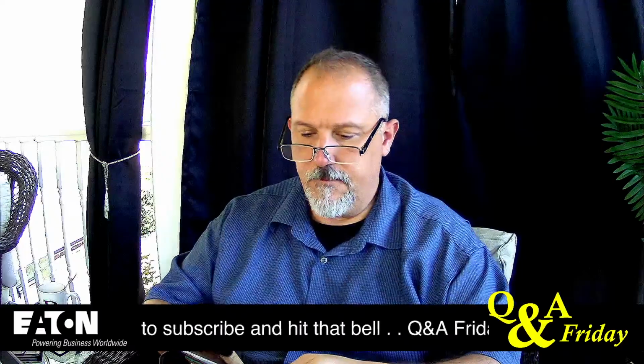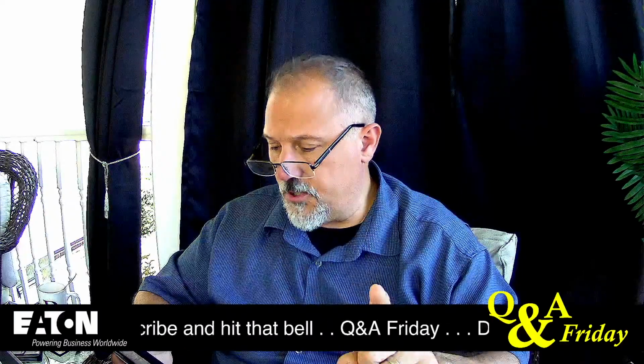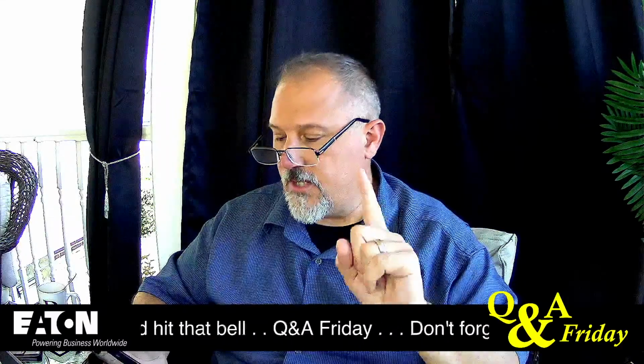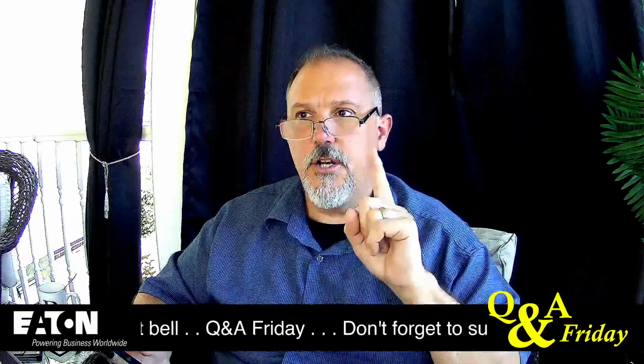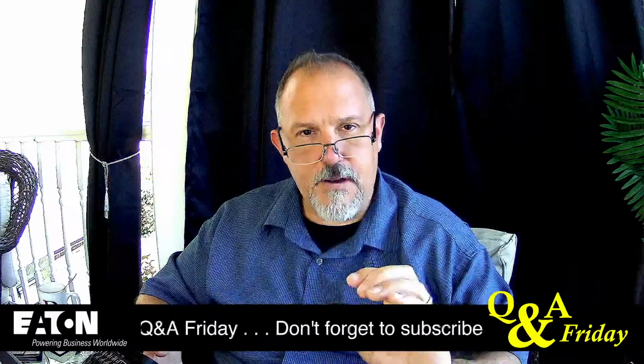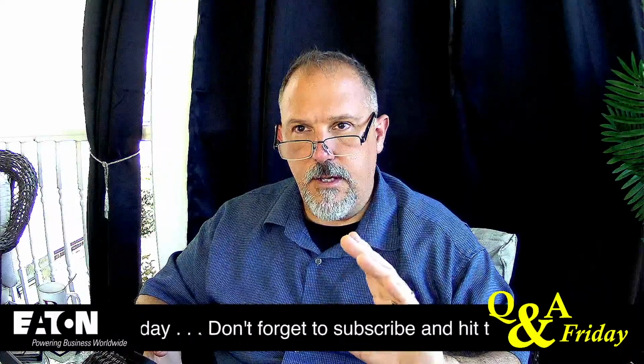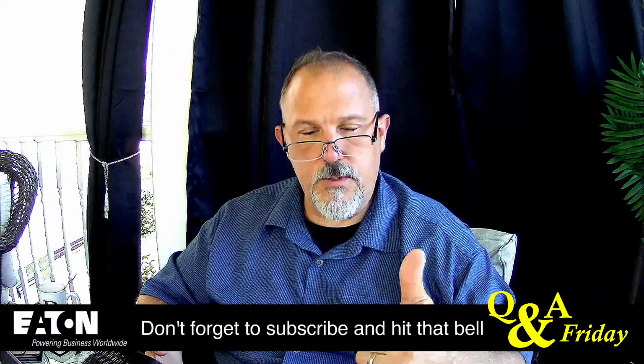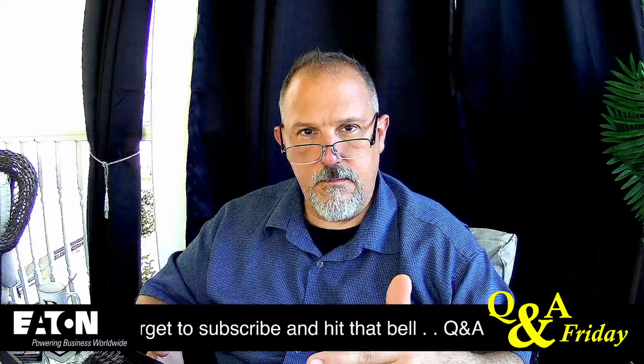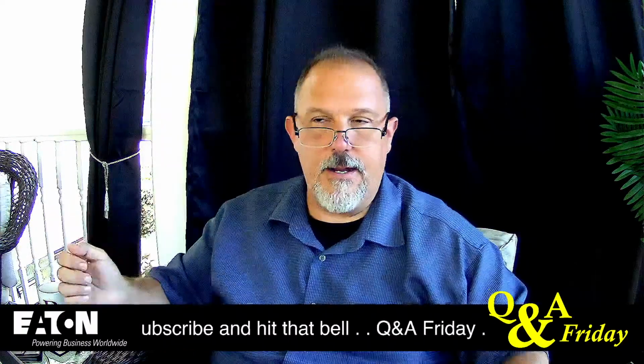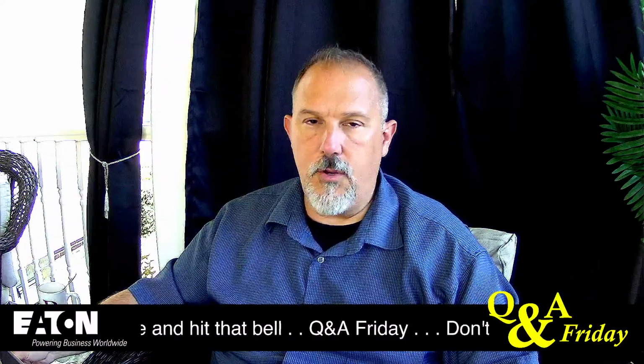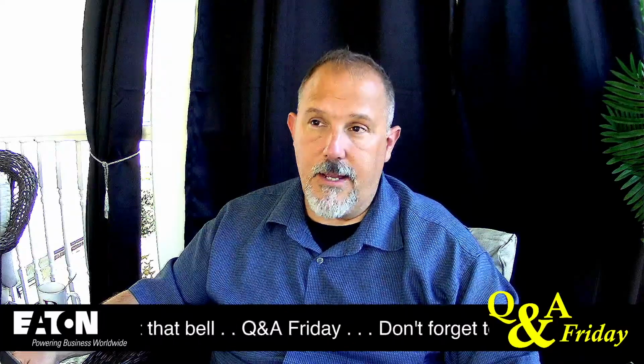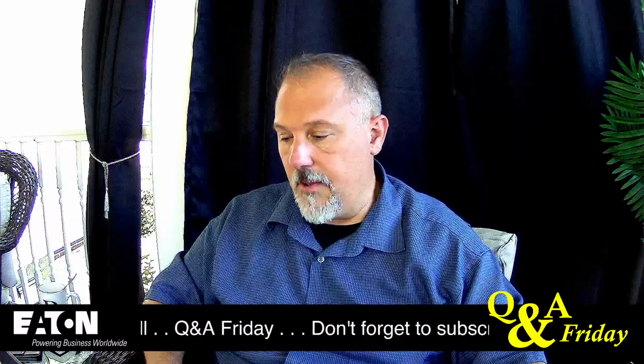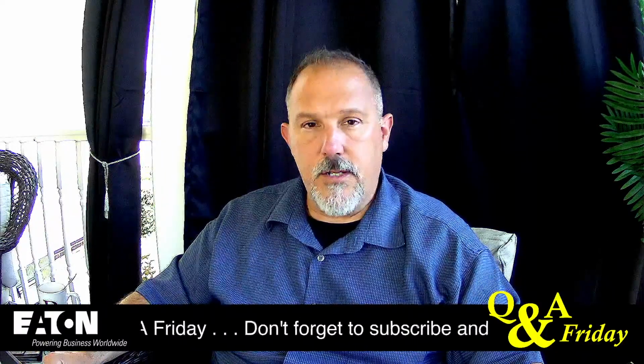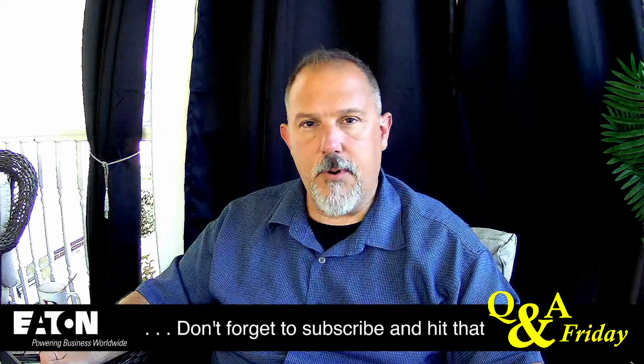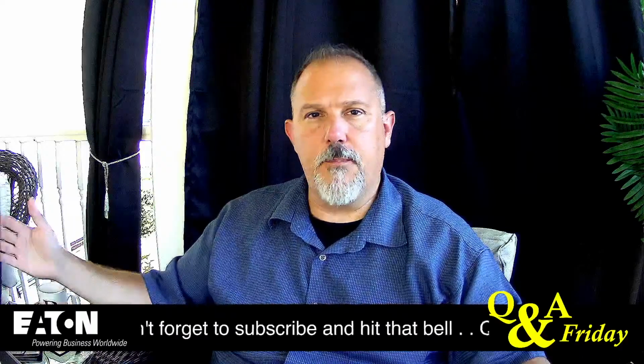I think your assumption is correct. I would say your assumption is correct. You've got to go to the upstream, unless you find a motor control center that is either listed or tested to a standard that recognizes compartmentalization. That would be my suggestion. I can tell you the likelihood, but again, it's my opinion, right? And I don't know that any manufacturer would go out on that limb to say you will not have line side propagation. That's really what you're worried about, based upon the proximity of where you're at and the equipment.